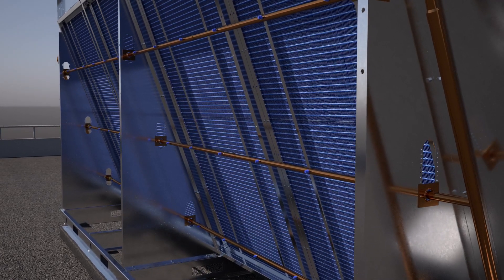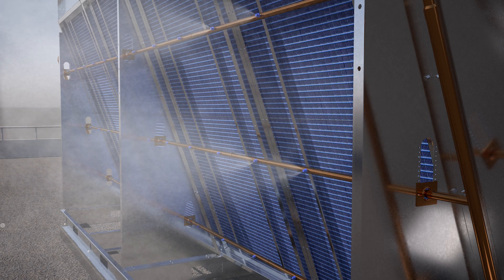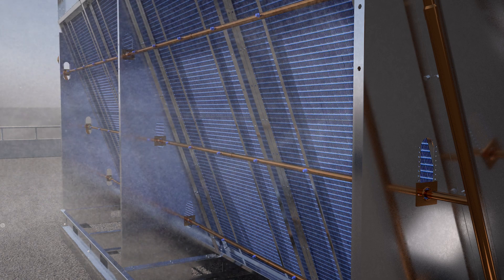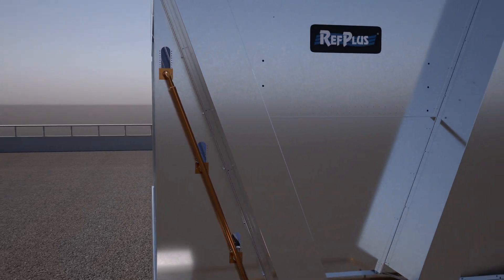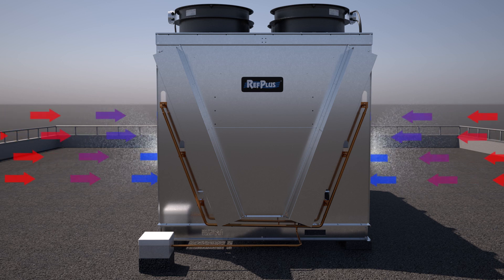It uses a natural air cooling process by evaporating a small amount of water through an array of atomizing nozzles. When the unit cannot reach the necessary cooling capacity, the nozzles start generating a fog of ultrafine water droplets. The resulting water mist absorbs the heat in the air to cool it down before it enters the unit's coils.